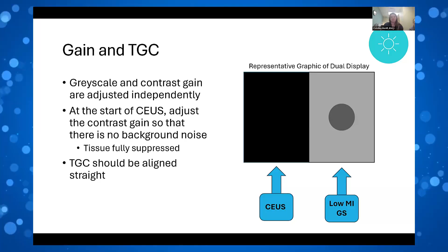In order to know that our gain isn't too high, you can use a trick that is conventionally taught for color Doppler, where you turn the gain up until you get some speckle, and then you turn it back down until that noise disappears. So you know that it's close. That way you know that your gain isn't set too low, and by eliminating the speckle, you know your gain isn't set too high. Your TGCs also should be aligned straight at the start of your CEUS.